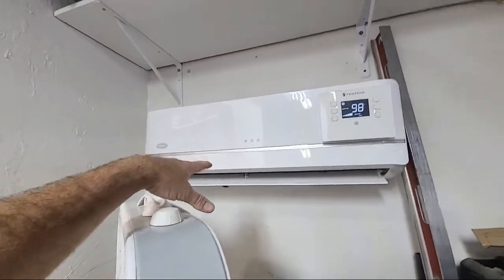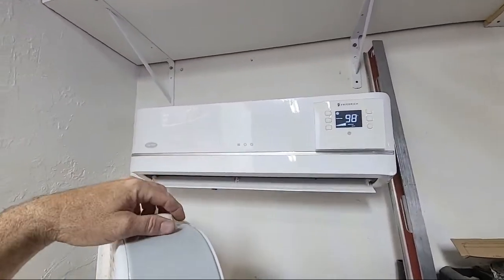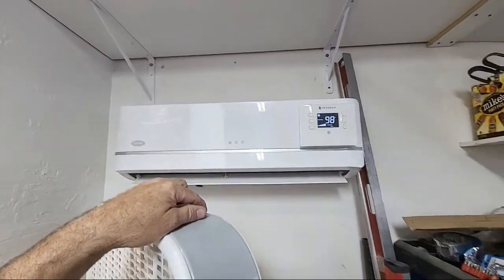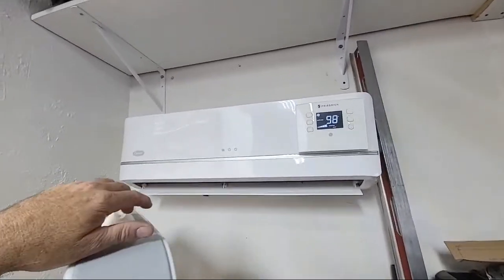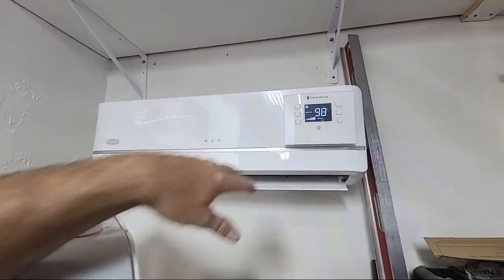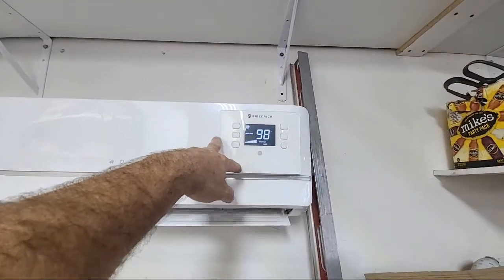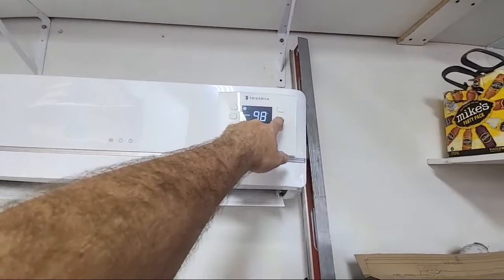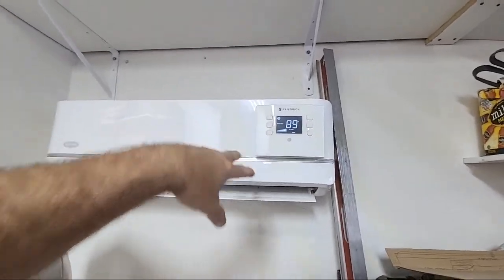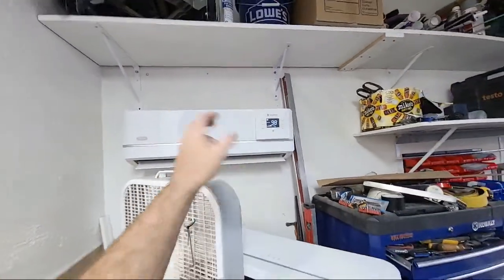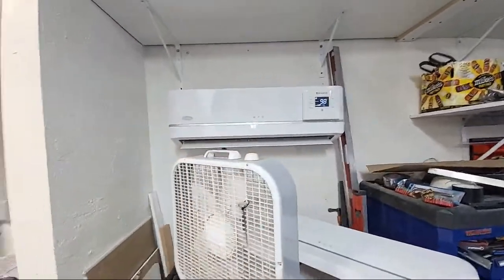The outdoor unit is a Friedrich package, what they call package VRP, variable refrigerant product. It's basically a VRF in a package. That's why it's a Friedrich controller, because it's controlled and it talks to the unit out there through data. And then I had to take the coil sensors and everything and hook them up to out there, because I took off the evaporator section of that package, vertical package unit. It goes in hotel rooms and whatnot, in closets.